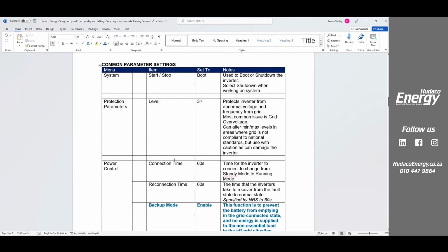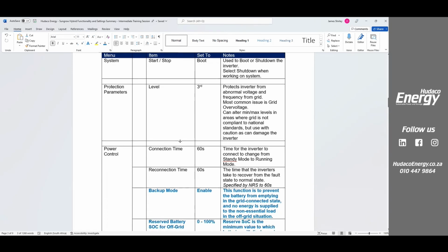In the menu system, the client, in other words the end user, has access to these common parameter settings. So the next few things we're going to go over are the things that the client can control themselves. You'll see I've got a lot of things in black. I've also got some things in blue. The things in blue are the settings which we're going to change when we're doing commissioning, or at least look at and potentially change if they're not at default. All the rest are the default settings, which selecting NRS will automatically take you to, but it's good to know that you can change them if you need to.